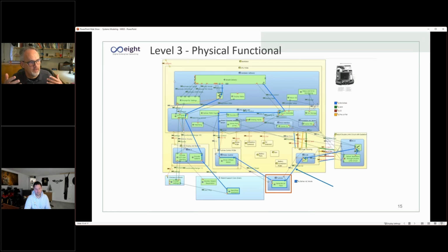to one another. So one of the things I like to say is that the systems modeling gives us a positive view of the design. And what that means is, what do we want the design to deliver, right? What functionality do we want it to provide? Risk management is really a negative view of the design that says, what do we need to have in the requirement set to assure something bad doesn't happen? So it's kind of both sides of it, the positive view of it and the negative view. So this is really, how do we determine what needs to be delivered in the device from a functional standpoint so that we can represent that as requirements in the requirement set.